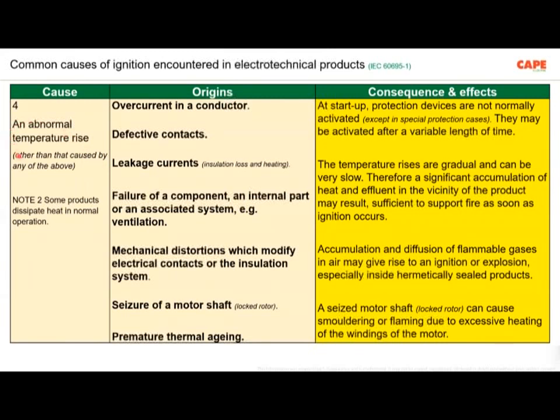And the fourth cause is abnormal temperature rise due to overcurrent in a conductor, probably due to a defective conductor, probably due to leakage current, loose contacts, failure of a component, mechanical distortions, seizure of a motor shaft. That means the motor is locked and the motor is not running. Premature thermal aging. Why I am showing all these reasons is, there are several reasons which could ignite a fire in a building. Generally, we call this arc, spark, overload, short circuit, earth fault, and so on. But if we go into depth, there are several reasons, and there are established methods to investigate or to analyze such problems or failure analysis. These are actually very well documented in the standard.